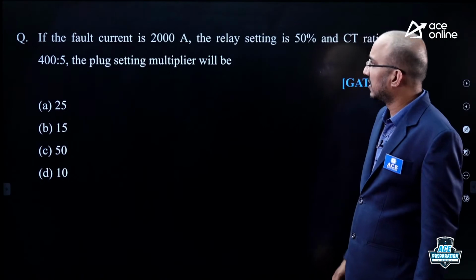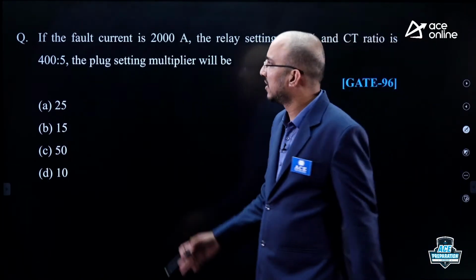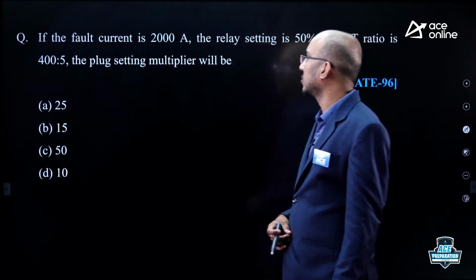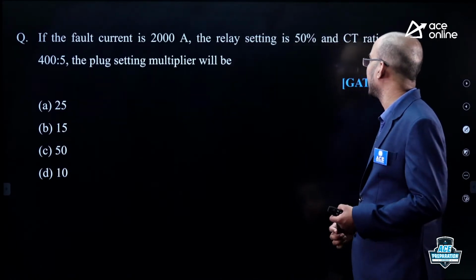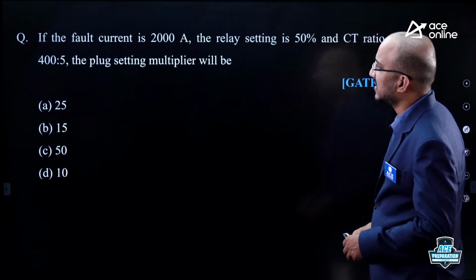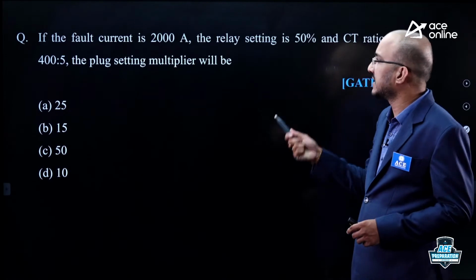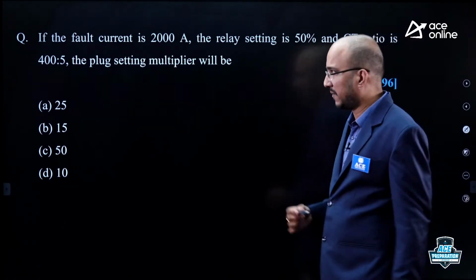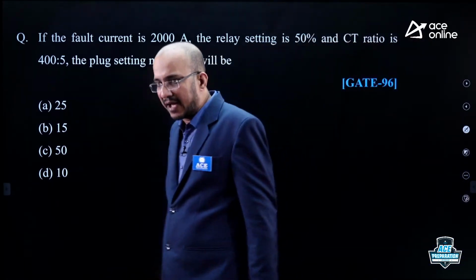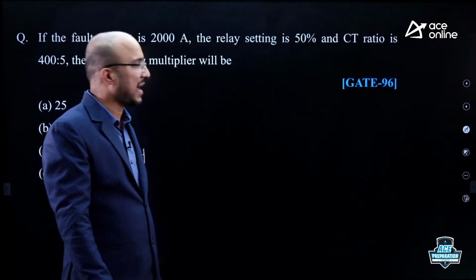Okay. Now, let us observe this question. If a fault current of 2000 amperes, the relay setting is 50%, CT ratio is 400 by 5, we are asked to calculate the plug setting multiplier. This is one of the important areas where the question is frequently asked.